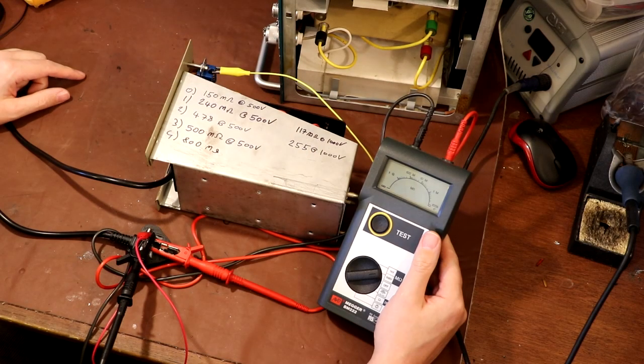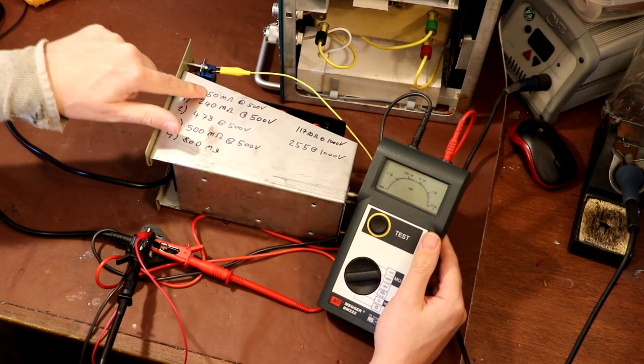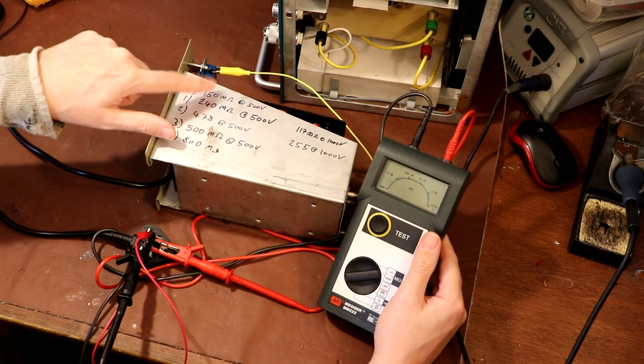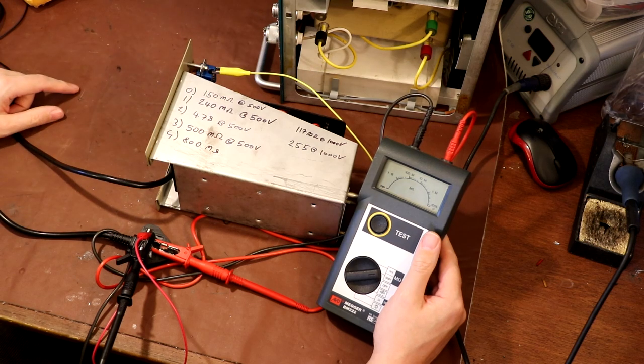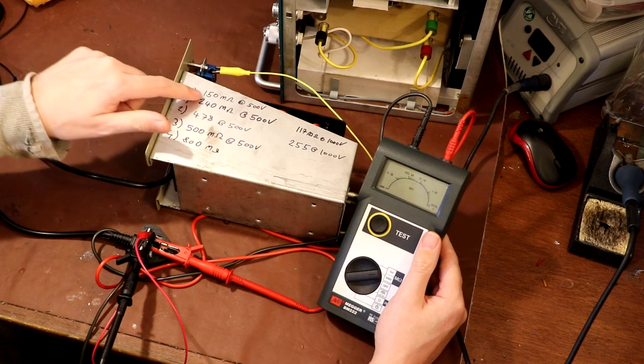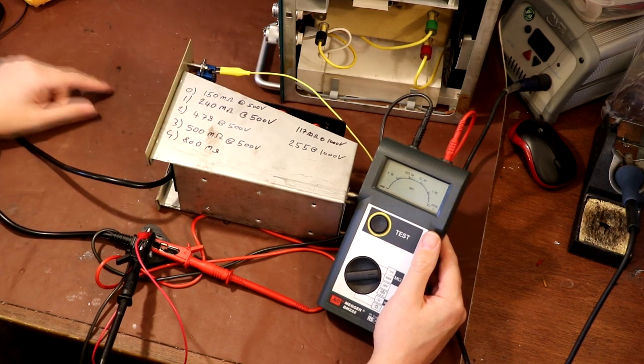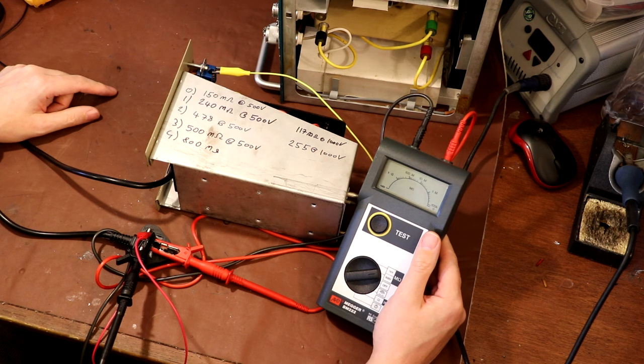Now previously you saw that I had a problem with this power supply tripping out the earth leakage circuit breaker, and I did an insulation resistance test, and actually the transformer wasn't coming up too bad. I think initially it was coming up about 150 megohms, which actually isn't too bad a reading. Generally that wouldn't concern me, and if you do a back of the packet calculation, that comes out at not very much, around 6 microamps leakage.